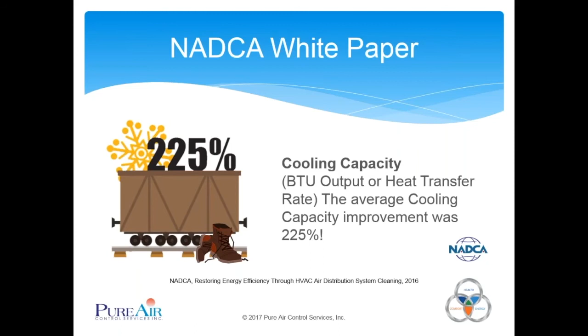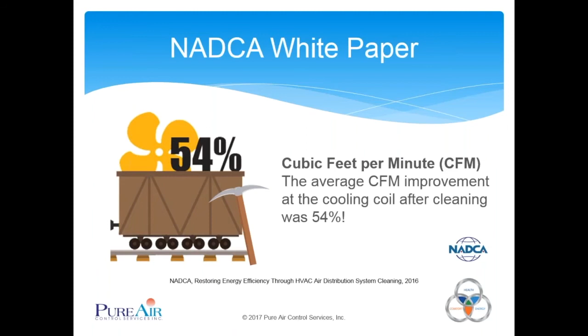And then finally, the cubic feet per minute, there's that answer. The CFMs. The average CFM improvement at the cooling coil after cleaning was 54%. So the study's findings, to quote the actual study, were that coil cleaning made significant improvements on the vast majority of jobs. This was compiled by NADCA's Energy Field Trials Task Force, which studied the improvements after HVAC cleaning.